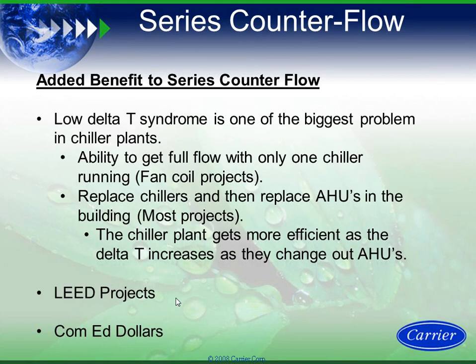Added benefits to series counterflow. I call this the Band-Aid, right? The biggest problem of a chiller plant is low delta T syndrome, okay? How do you solve low delta T syndrome? Well, you have to try to somehow handle your coils and your air handlers and fix that part of the building in order to increase the delta T of the system.